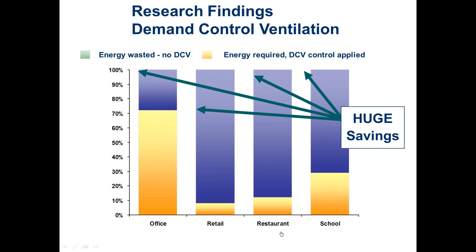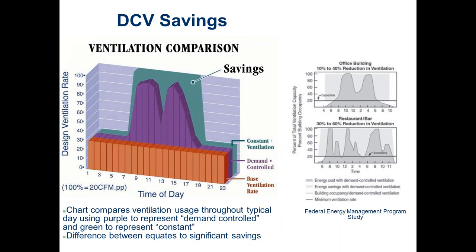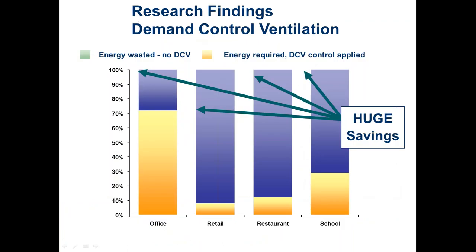Typical averages for energy savings: an office building saves about 30% of ventilation energy by adding DCV — basically 30% of the time the building isn't fully occupied. Retail shows massive savings of about 90%, because those spaces are sized for peak events like Black Friday but are mostly lightly occupied. Restaurants similarly show about 90% savings potential, since they're designed for Saturday night dinner crowds but are lightly populated Tuesday morning.